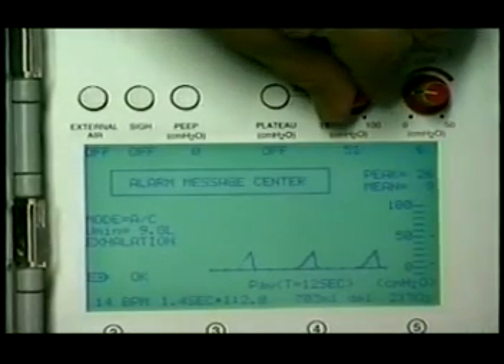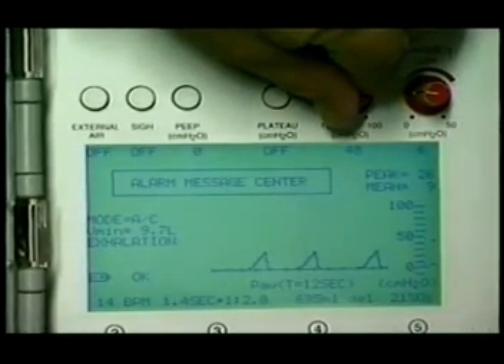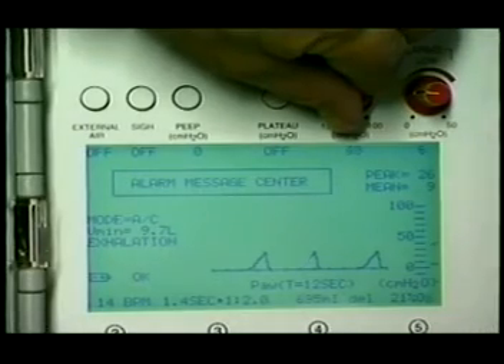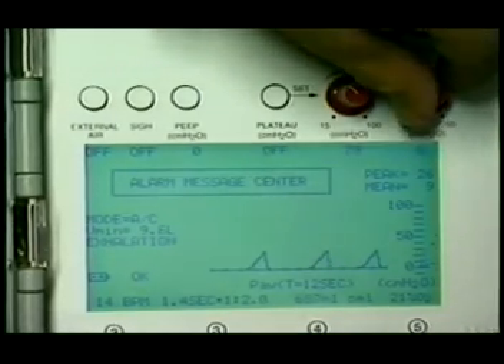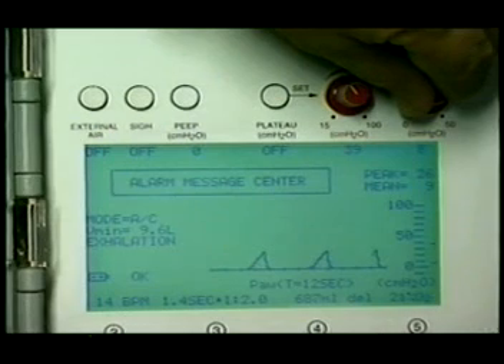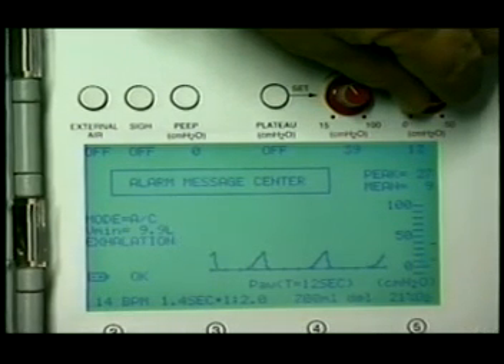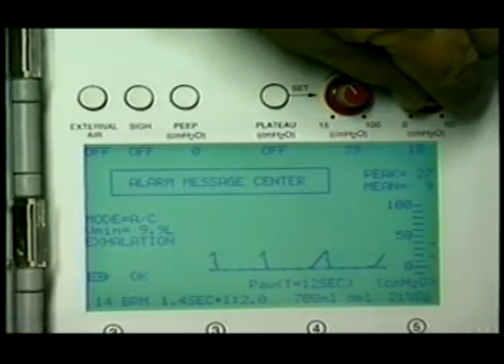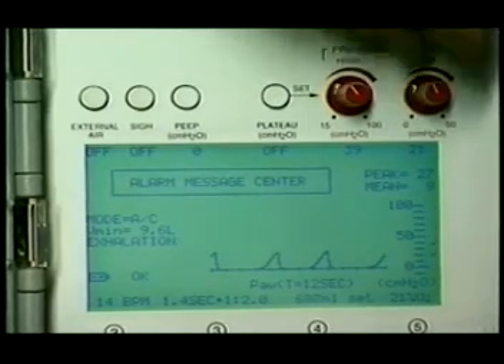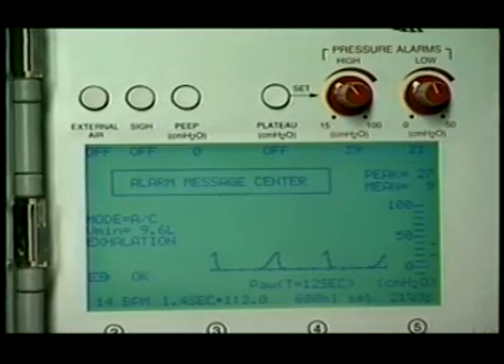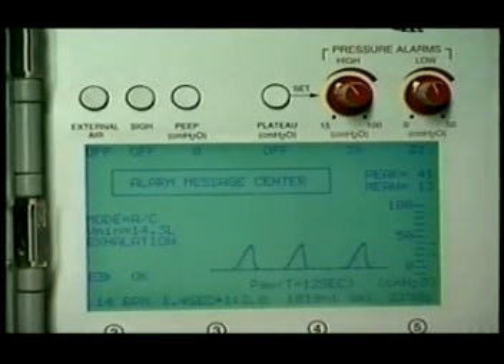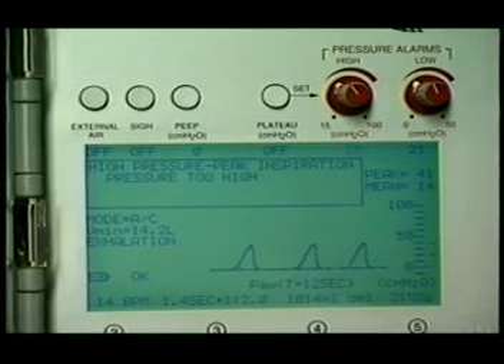Notice the tick movement as I adjust each control upwards or downwards within a safe proximity on either side of the peak airway pressure. In this case, peak airway pressure is 27 centimeters of water. The high pressure alarm limit is set for 39 and our low pressure alarm limit is set for 21. If the patient's peak airway pressure exceeds the high pressure alarm set point at any time for 4 consecutive breaths, it will trigger the high pressure alarm.